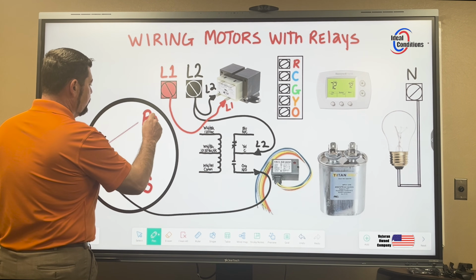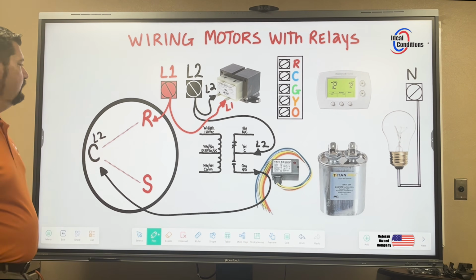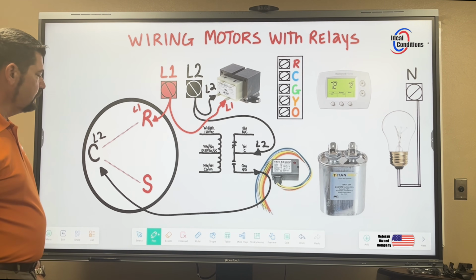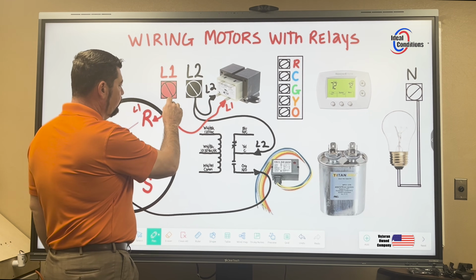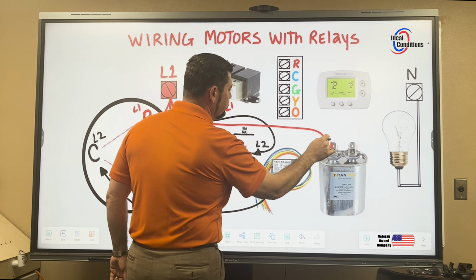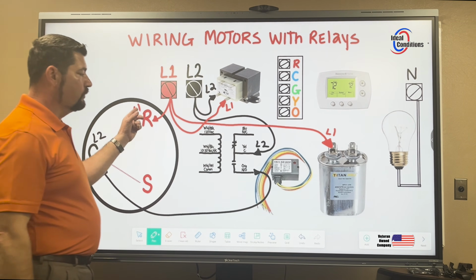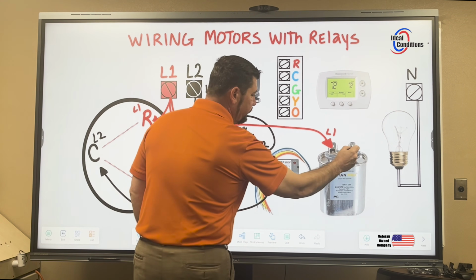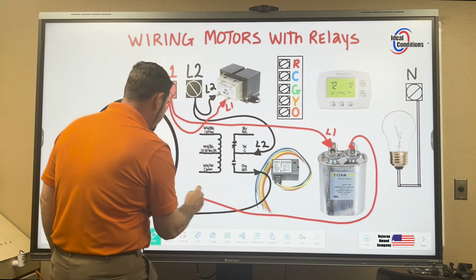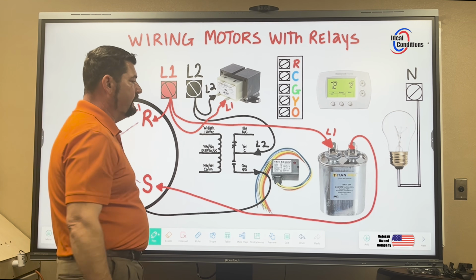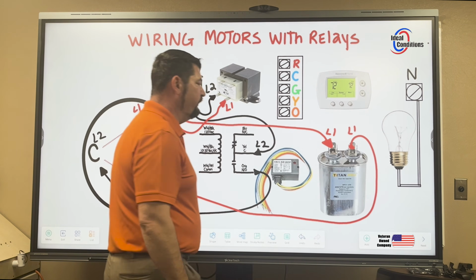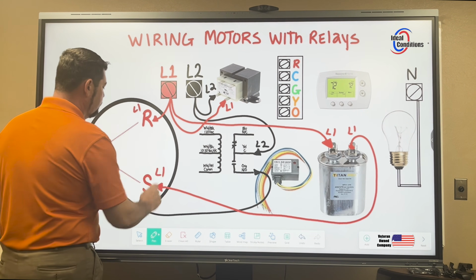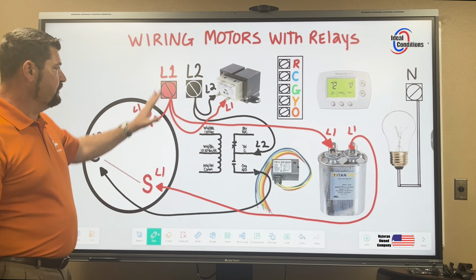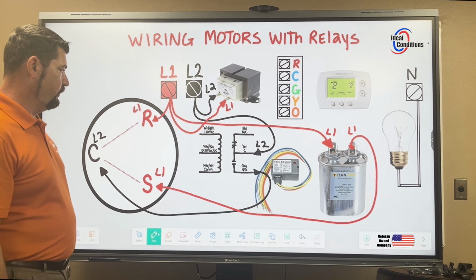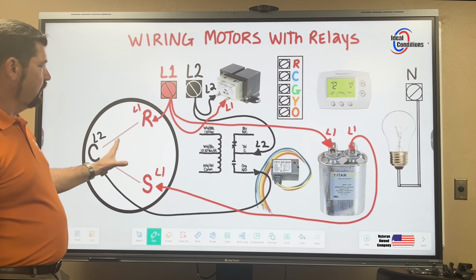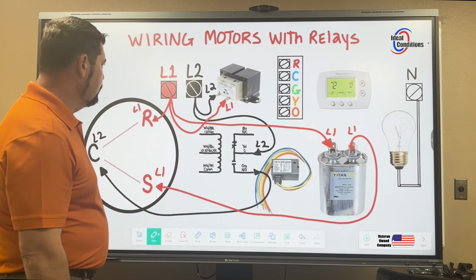We're going to come down here and we're going to go ahead and run L1 over to our run winding. Okay, we're going to go ahead and label that L1. And the next thing we need to do to complete this circuit is we need to energize the run capacitor. So it needs a leg of power on it, the same leg of power that the run winding has. And then out of this capacitor, we need to come out and we need to energize the start winding. So this capacitor is providing a third leg of power. However, we don't call it three-phase. It's single phase. There's only two legs of power here. But what you need to understand is on two of these windings, it will always be the same leg. The other winding will be the other leg. So we have everything done on the high voltage side, and we are ready to wire up the low voltage.